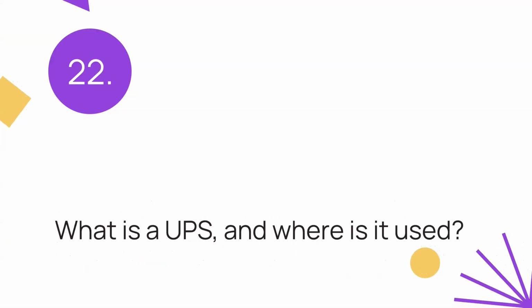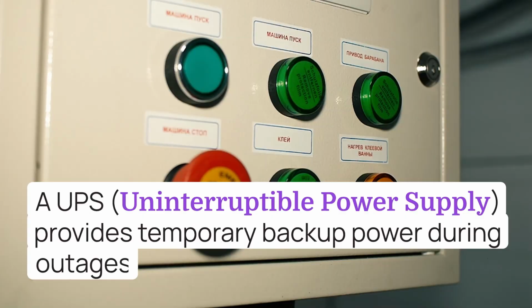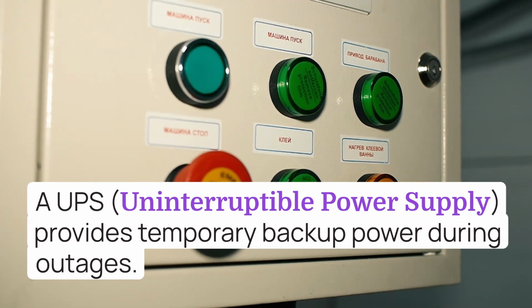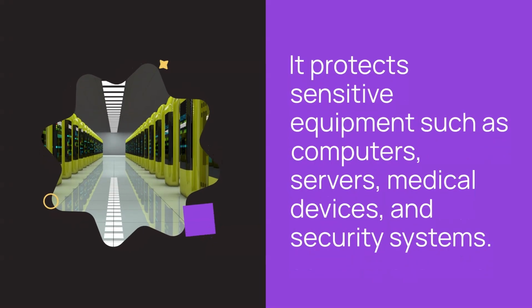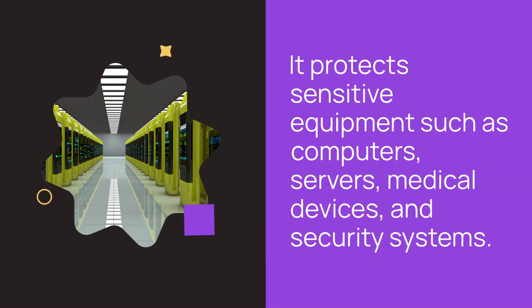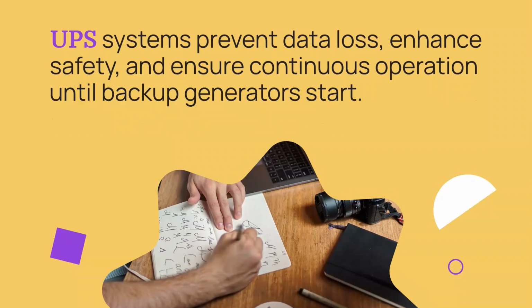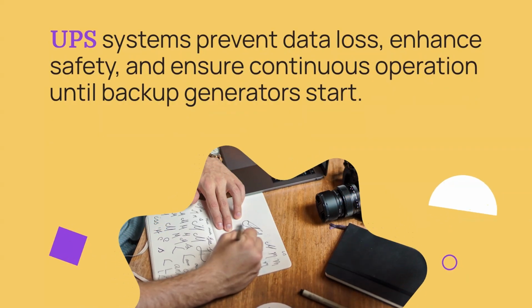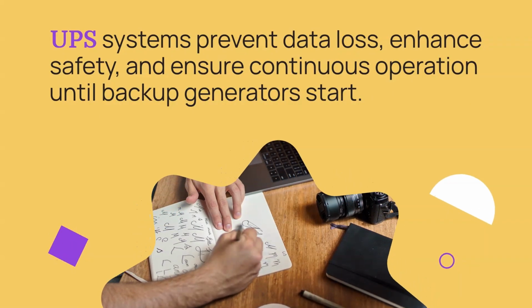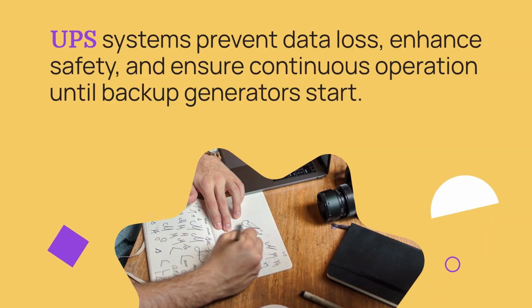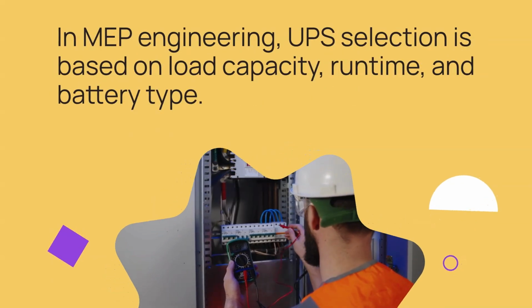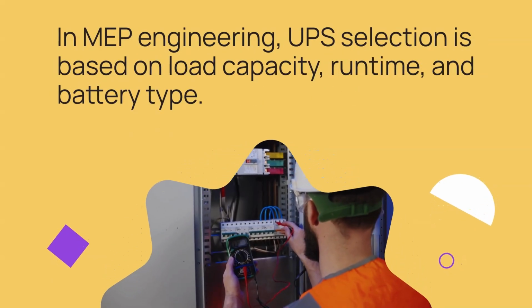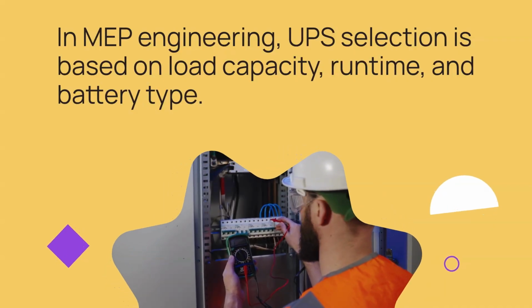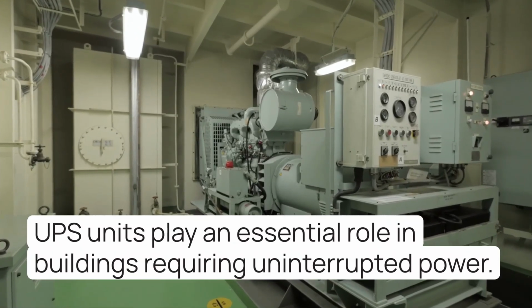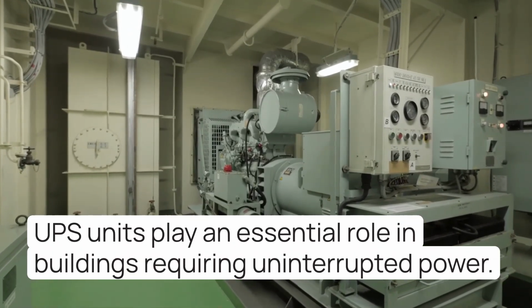22. What is a UPS and where is it used? A UPS, uninterruptible power supply, provides temporary backup power during outages. It protects sensitive equipment such as computers, servers, medical devices, and security systems. UPS systems prevent data loss, enhance safety, and ensure continuous operation until backup generators start. In MEP engineering, UPS selection is based on load capacity, runtime, and battery type. UPS units play an essential role in buildings requiring uninterrupted power.